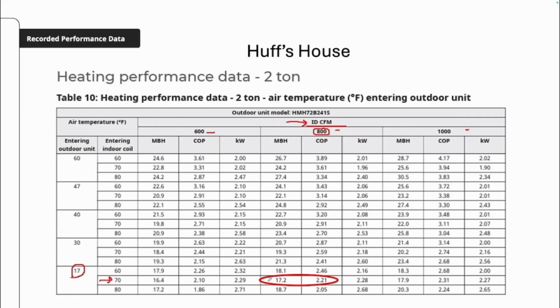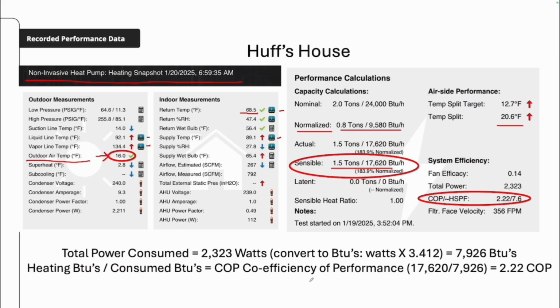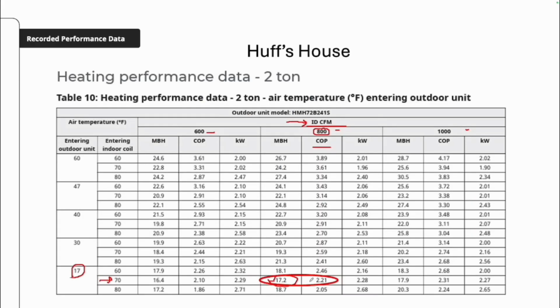Based on those conditions, my outdoor temperature was 16 and my return temperature was a little under 69. So it's still very comparable. But at that temperature, the chart says 17.2, which is 17,200. And notice the COP, it also gives a COP in this column here, and it says it should be 2.21. That's what the manufacturer says the equipment's capable of under those conditions. What is my system doing? It's outperforming it by a couple hundred BTUs. And again, being within 10% is what the OEMs consider acceptable. And my COP is 2.22. So I'm actually outperforming what the manufacturer says that system can do.